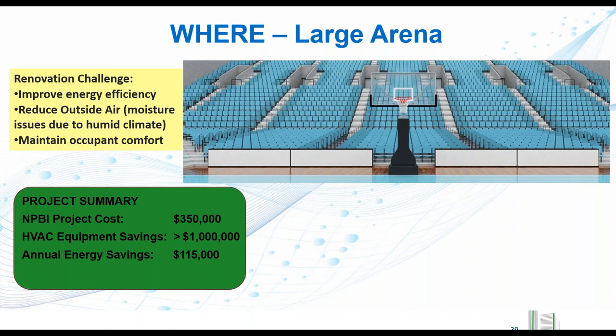Additionally, because that outside air wasn't having to be cooled, dehumidified, and in rare instances heated in the winter, there's an energy savings associated with that, and it was $115,000 a year. So the needlepoint bipolar ionization return on the investment is immediate. The beauty of it was bundled with the entire package. Chillers are expensive, pumps, motors. Doing this kind of a retrofit is very expensive. It helps bring the overall payback of a project down.